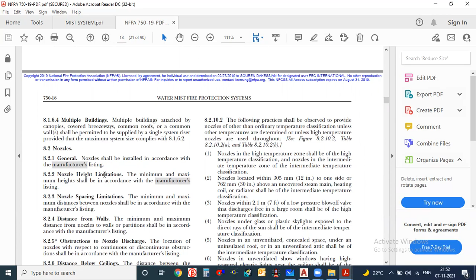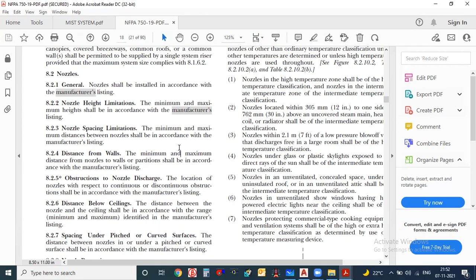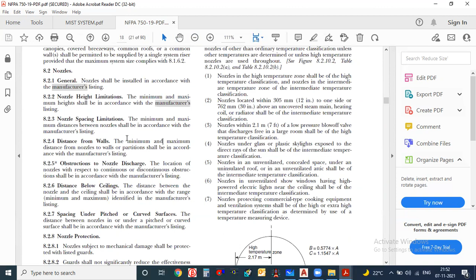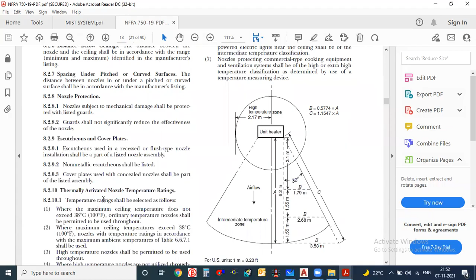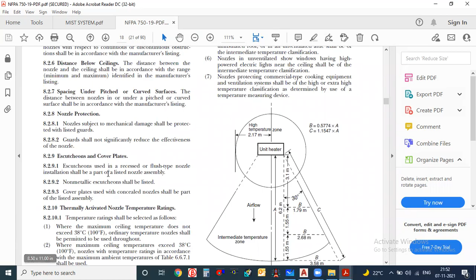Okay, they have given something. Nozzle height limitation, at what height it should be installed. So here they have clearly mentioned that the minimum and maximum height shall be in accordance with the manufacturer's listing. So you need to go with the manufacturer, like what is the preferred height and what is the minimum and maximum height. Even they have given the distance from the wall also. The minimum and maximum distance from nozzle to wall or partition shall be in accordance with the manufacturer's listing. Distance below ceiling, obstruction to nozzle, everything they are telling to check with the manufacturer. Whenever you are selecting a mist system, just check with the manufacturer and select accordingly, as per this document I am telling you. Then thermally activated nozzle temperature ratings. Okay, they have given something about the sprinklers here. So you can just check these things.